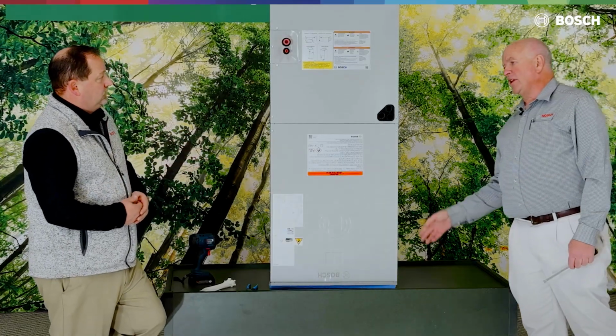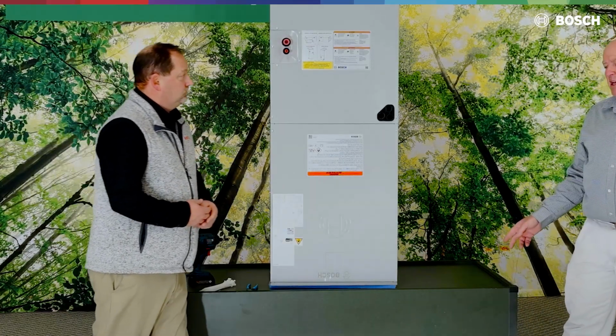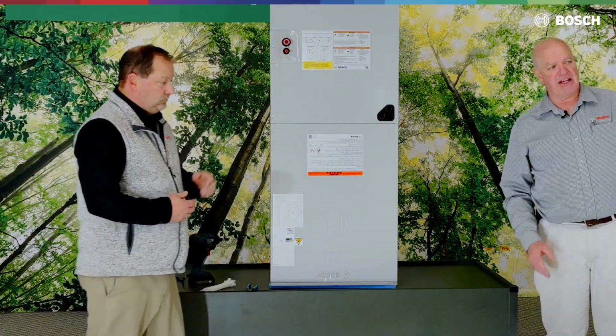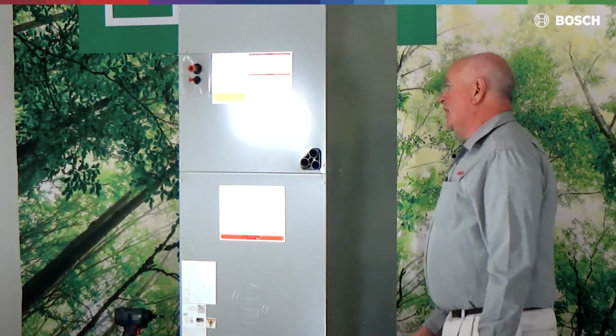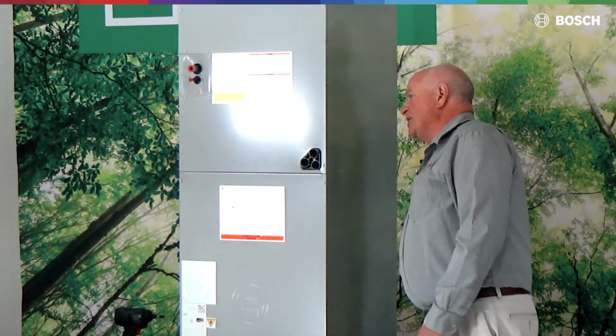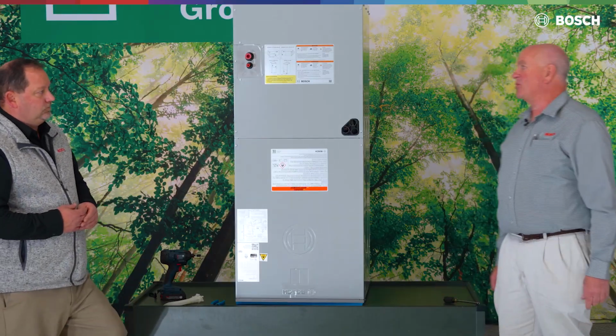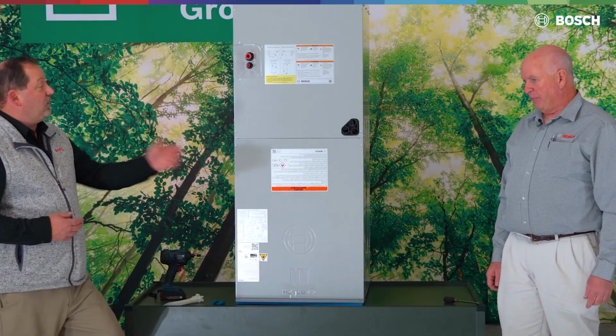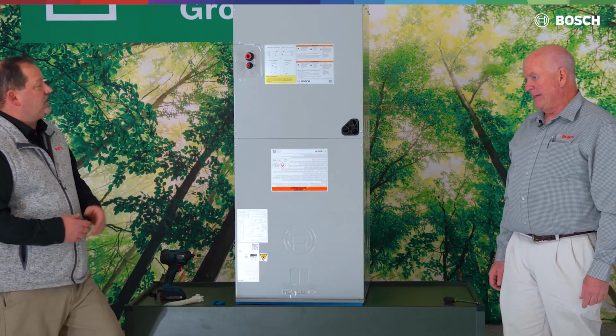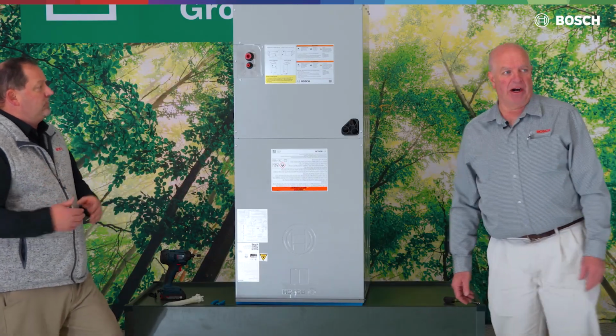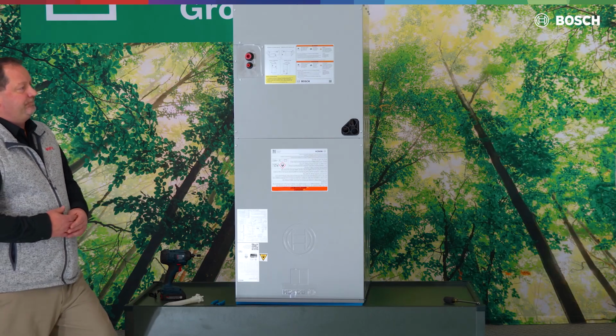I believe with electric heat, on the bottom of the unit, if you have electric heat, you can't put it on a combustible base. It has to be a non-combustible base, so if something would malfunction, we don't catch the home on fire. So we have to be aware of that non-combustible base if we're going to do it in a downflow, electric heat application. Does Bosch have a combustible floor base, or is that something that you have to make? I would say that's out in the field, aftermarket. I don't think Bosch has that. That is aftermarket as well.